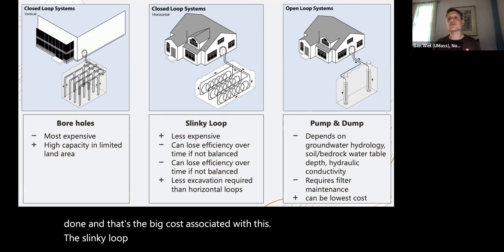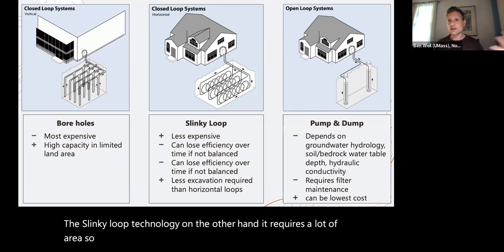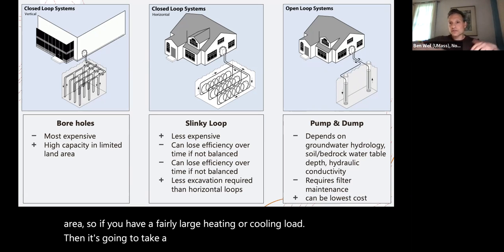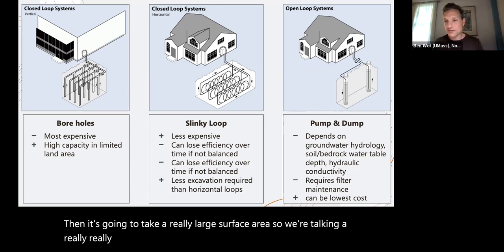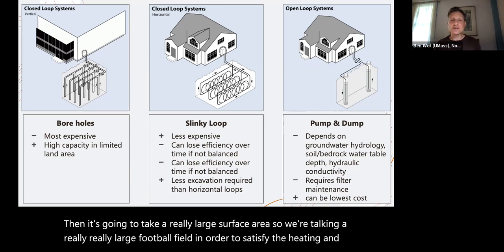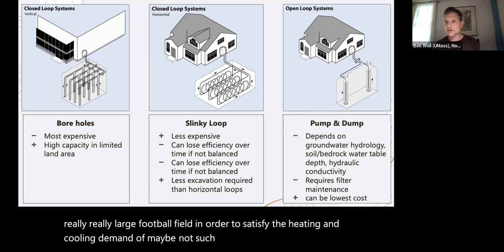On the other hand, it requires a lot of area. So if you have a fairly large heating or cooling load, then it's going to take a really large surface area. We're talking a really, really large football field in order to satisfy the heating and cooling demand of maybe not such a huge school, for example.